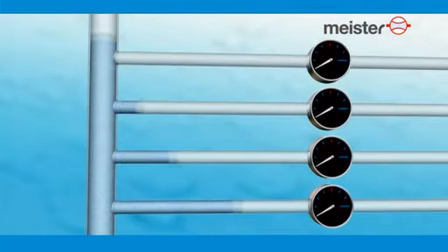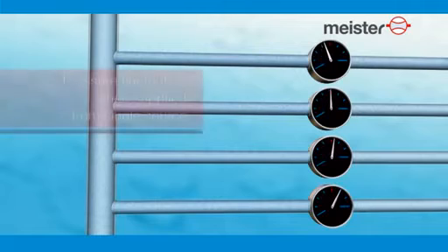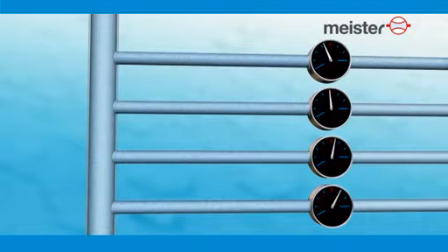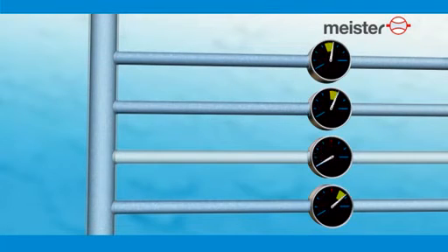Pressure fluctuation can occur any time water is supplied to multiple devices from a single source. These fluctuations cause considerable variation in the flow rate when the valves are adjusted to a fixed position. When one device is shut off, the pressure at the other equipment rises and water is wasted unnecessarily.